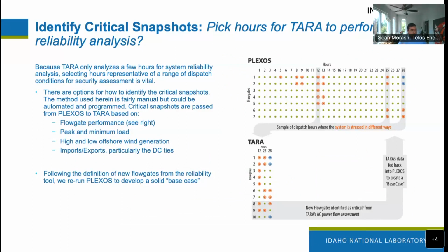We're using a DC power flow in the production cost model PLEXOS. But we want to double check if we're being secure with how those resources are dispatched to meet load, right? Are we accidentally glossing over some really key transmission congestion issues, really key transmission problems? And so we had a pretty rigorous process to better inform our operational analysis with an AC power flow simulation, right? And so this process, it's funny, it winds up in this graphic that looks pretty slick, but it makes it look simple.